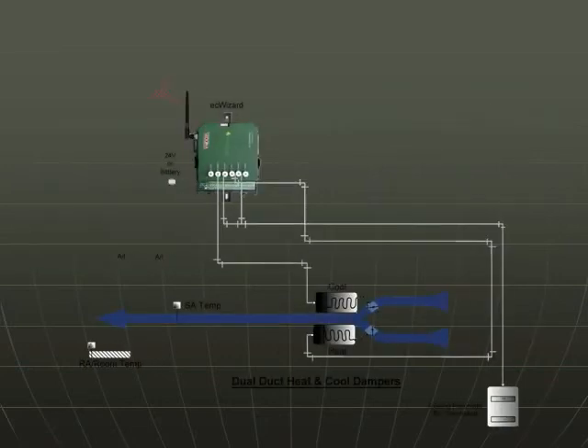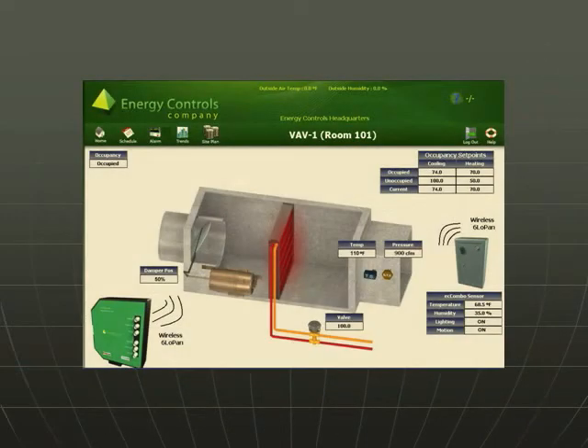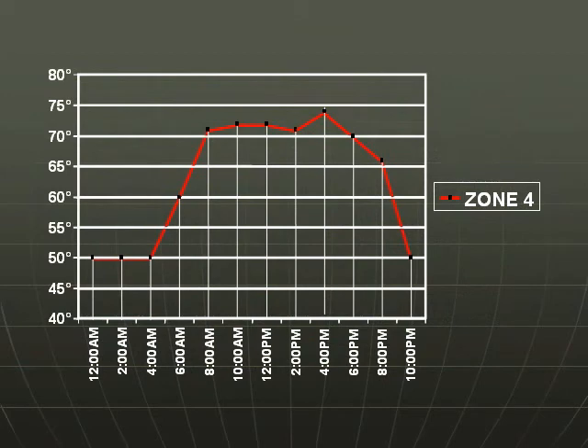Double-duct zone systems quite often waste energy. These systems depend on tight close-off of the heating damper when in cooling mode, and tight close-off of the cooling damper when in heating mode. The ecWizard provides the diagnostic capabilities to find these known problems with the double-duct zone controls. System diagnosis with trend logs and monitoring provides economical, fast solutions to temperature discomfort and energy wastes.